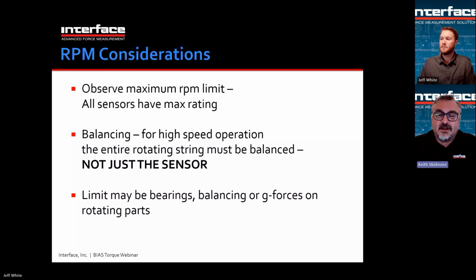So a sensor might be rated for 30,000 RPMs at 1 Newton meter, and then the 1,000 Newton meter version might only be rated for 5,000 or 10,000 RPM. That's pretty much a law of physics. It doesn't change. Somebody says, "Oh, I want to buy that sensor that's rated for 30,000 RPM at 1 Newton meter, but I need it at 1,000 Newton meters, and I still want it at 30,000 RPM." Well, if that were easy, we'd already have done it. It would be the specification. So the fact that it says it can only run at 5,000 RPMs, that's a pretty hard limit. Not like, oh, we'll just have to do something else. Because if that something else was easy enough to do, we'd have already done it.